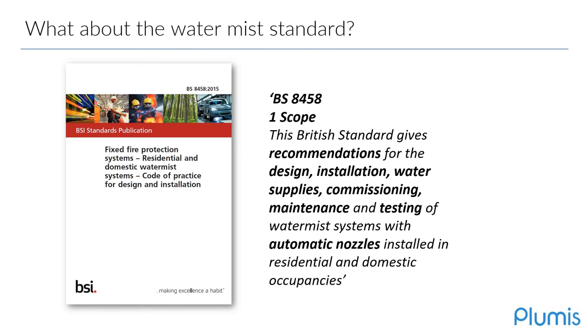So let's have a look in more detail into 8458. Well, just looking into the scope of it in clause number 1, we can already learn a lot of what is its objective. Firstly, it is a code of practice. It is stating that these are recommendations, so they're voluntary recommendations, they're guidance, they're not the law. You're not obliged to follow them. However, if you choose to follow them, you should declare how you're following them and how you're not following them if you are deviating in any of the clauses.